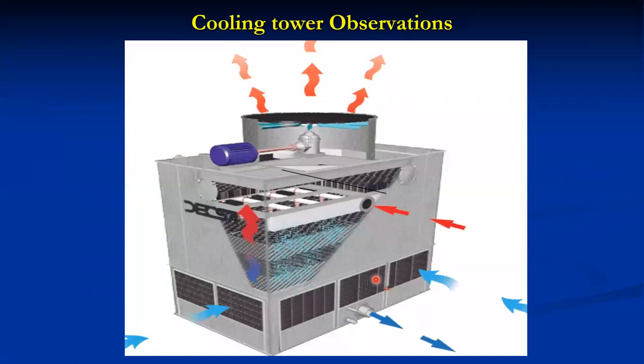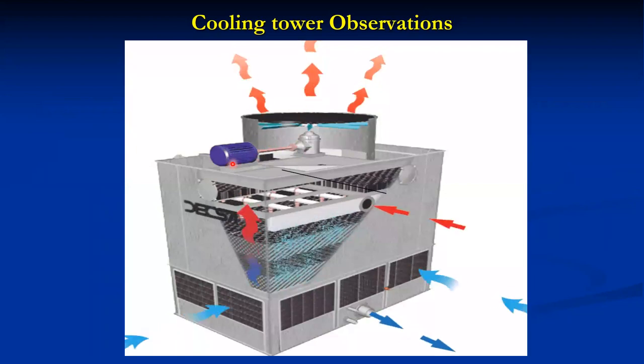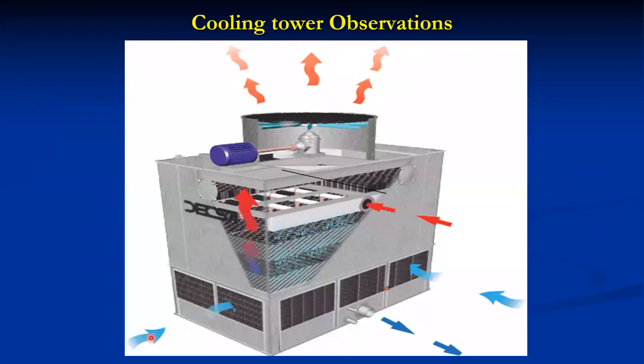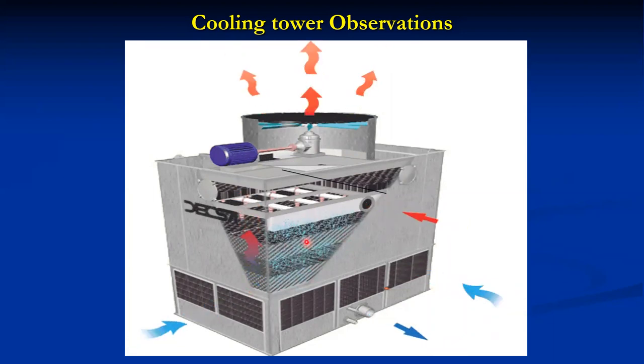This is the virtual setup of the cooling tower — an induced draft cooling tower because the fan, motor, and blades are fitted at the top. Air enters from the sides. Water enters into the cooling tower from the condenser, and through a common header it is sprayed over the fill material. Air and water come in contact with each other in a counterflow arrangement. The air takes away heat and some water evaporates, cooling the water, which is then sent back to the condenser.